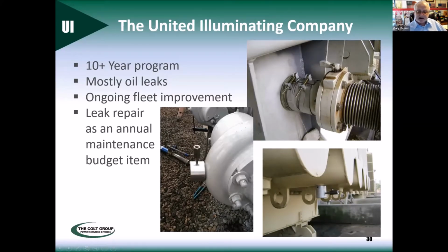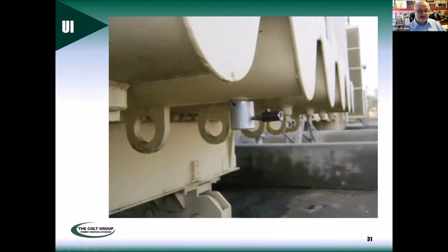These are knock-on caps. I'll show you that in a second. These knock-on caps have a labyrinth seal to them, like crunch teeth. I'll show you in a second, but they're designed to knock them on the half coupling right there, and then you put the set screws down on it to keep it from moving when you pump it. We know what the ODs on those half couplings are from 1/2 inch through 2 inch.